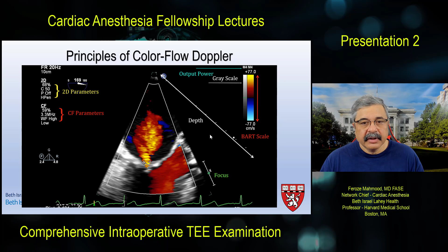Now you can take a look at these two controls that we've changed to demonstrate the impact on the color flow signal. The one on the left is a low Nyquist limit, everything else being equal. You can see that the upper limit of velocity either towards or away from the transducer has been reduced to about 0.3 meters per second, and that is leading to a lot of the turbulence being seen over here, which we otherwise wouldn't have been able to detect. So lowering the Nyquist limit means you tend to see only the lowest velocities, and you're unlikely to appreciate higher velocities than that, and anything higher than 0.3 meters per second will be seen as turbulence or aliasing, which is ambiguity in the direction and speed.